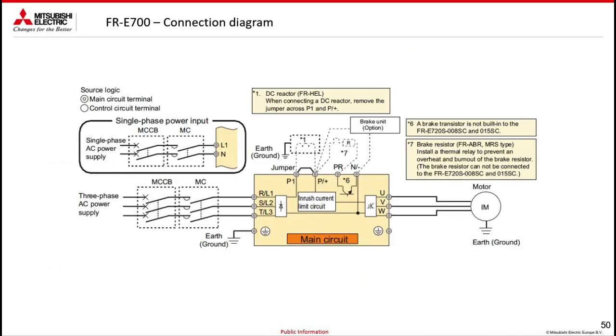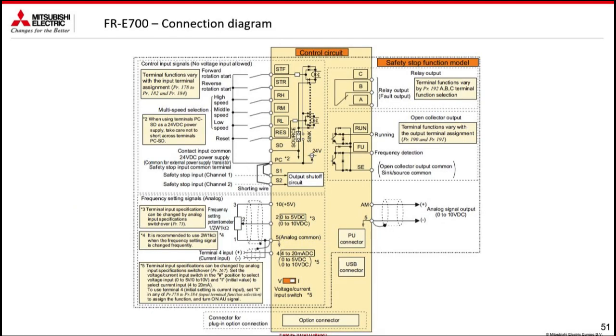As regards the connection diagram, I wouldn't dwell on it too much, as it is very similar to the FR-D700. As regards the signals, it is identical with the addition of the RES, so the reset. In fact, if the inverter goes into fault, it is possible to do a remote reset, which is not possible on the FR-D700 by default. What can instead be done is to sacrifice an input, which is then parameterized to have the reset function.